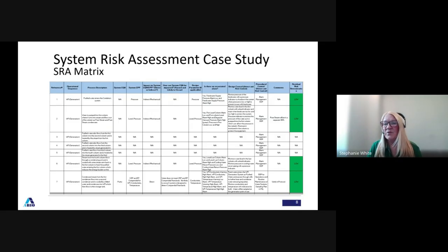Then we risk rank these. The ISPE Baseline Guide 5 for commissioning and qualification has a risk ranking table of high, medium, or low. Your goal throughout the process is to get your risk to low through the design controls you put in place.